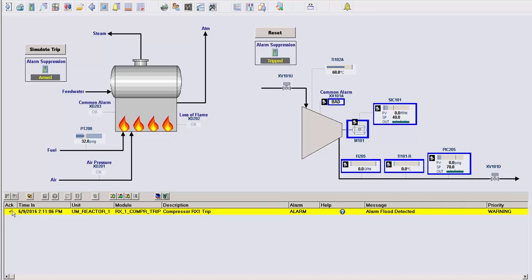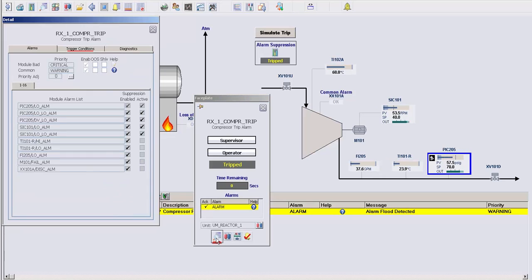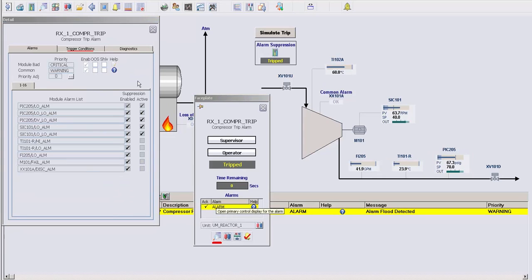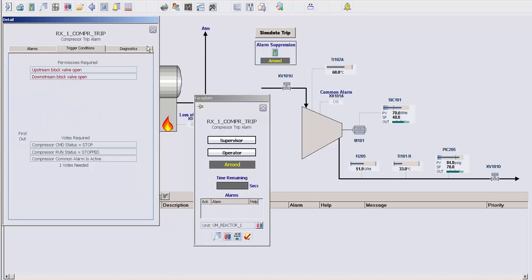However, in the case of both of these alarm suppression modules, these can be configured and downloaded to the Delta V controller without modifying the existing modules in any way. So in that sense, it's a very non-intrusive way of addressing alarms in a live running plant, requiring no downloads of existing modules at all.